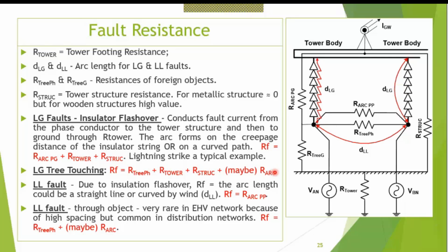The resistances may be quite high. But anyway, if we take into consideration the tree resistance, most of the things will be covered. There should not be much more. Normally if we consider 20-30 ohm tree resistance, your distance protection will pick up for most resistive faults also.